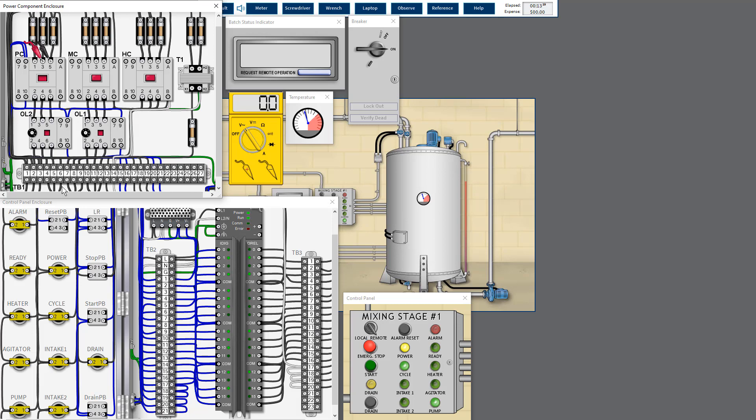You see, to run on three-phase, if two phases out of service or having open circuit, the motor will not run at all because the torque is not high enough to drive the current. And because only one phase is working instead of three phase, it will not bring the current anymore. That's why there's no issue over current. If there's no issue over current, the overload relay will not trip also.